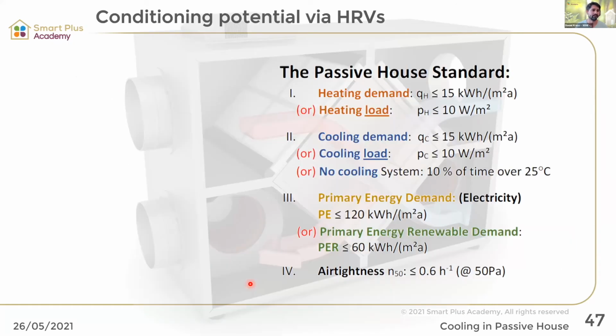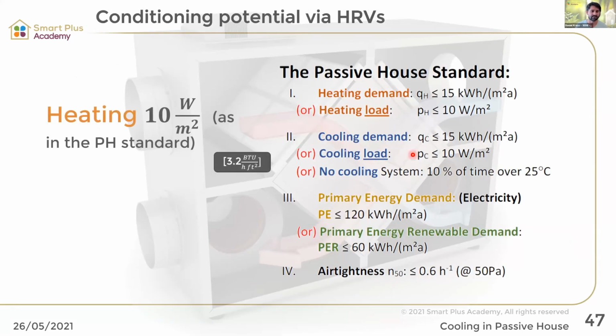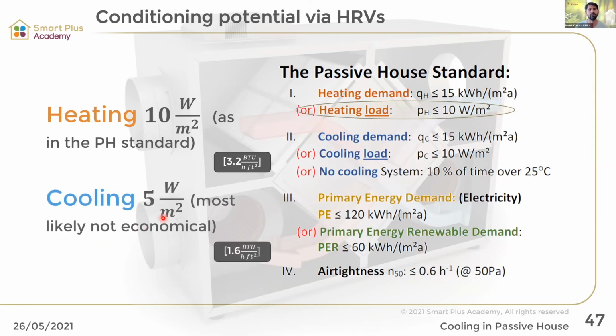When we're now looking at our passive house standard, we're seeing the 10 watts per square meter, use 3.2 BTU. That's here in our passive house standard. But the cooling has only a capacity of 5 watts per square meter and not the 10 watts. So if you're designing with a load of 10 watts per square meter, we can't use the heat recovery ventilation system or the supply air as our cooling medium. So how could we achieve that?